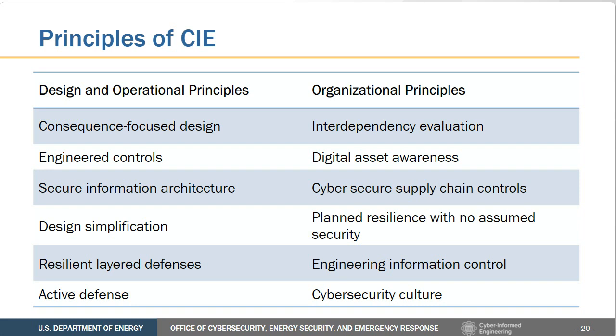So, for example, a 60% design review of a greenfield water treatment plant revealed that the design engineer replaced the manual handoff auto switches, which allow operations staff to run the plant manually, with a network-based communication device without manual overrides. The design team elected to undo this modification and justified the higher cost of construction with the benefit of assured manual controls in the event of a cyber compromise. So that's just one example of what we're talking about. We're thinking about designing in security foundationally. So maybe choosing to have manual overrides in places and not fully digitized systems to where there is no manual option.